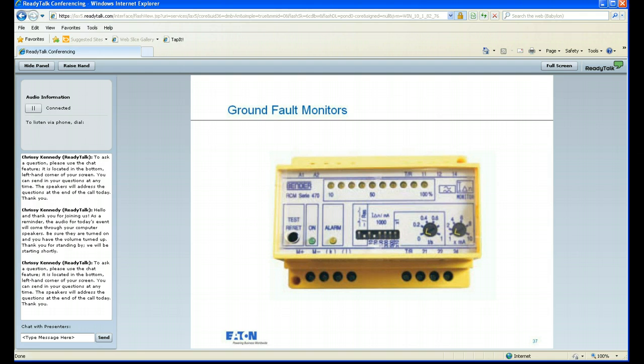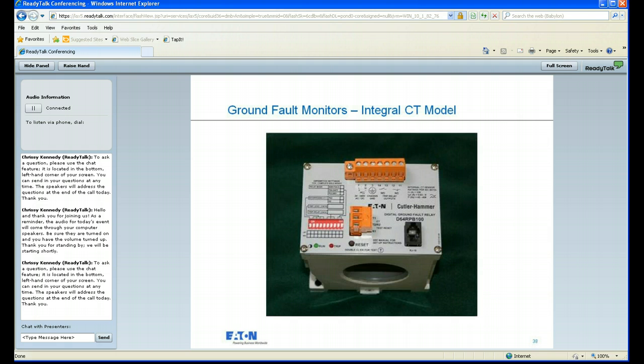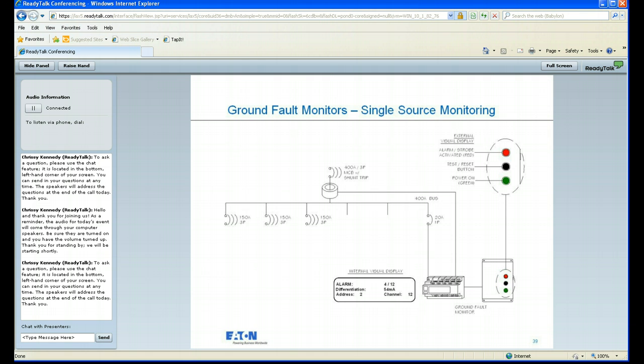The monitors are going to come in a variety of different shapes and sizes. This model by Bender, in my experience, is very easy to adjust. You can set it right at the 100 milliamp level, or if you're concerned with more leakage, or if you want to set it at that 15 milliamp level that could cause painful shock and muscle loss, you can certainly do that from this same device. It has a wide range of uses. You'll also see some ground fault monitors that have integral CTs where you're running your wires directly through the hole here at the bottom. Also a pretty easy to use and innovative solution.